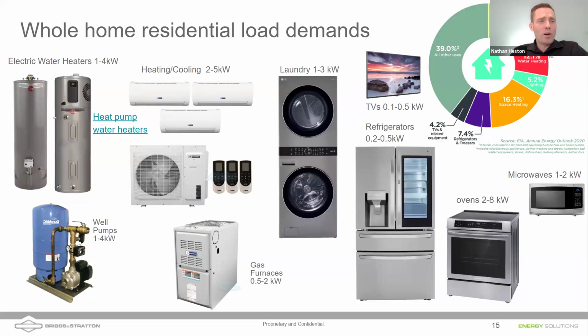The last version of this talk, I spent some time talking about all the loads in the home, the typical loads, heat pumps, well pumps, offering kind of big inductive drains on a system that can spike. And the Sol-Ark 15K has a surge ability. It can do 24 kilowatts from batteries for up to 5 seconds to start those large inductive loads like large air conditioner compressors, etc. But typical loads in a house can add up.